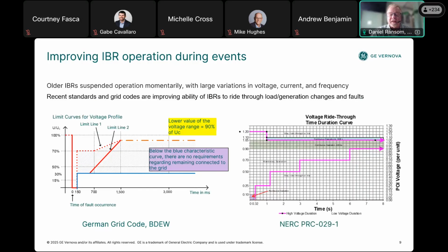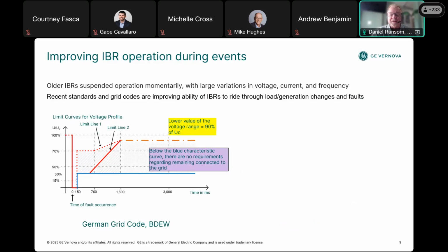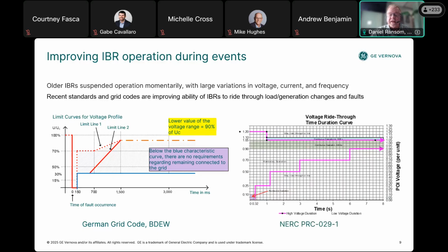It's the figure on the left. The figure shows the limit curves. We'll go back. It's the figure on the left. For type 2 IBRs, PV and BESS, these have to remain connected, as we'll see here in PRC-029-1, during a voltage drop down to 0% Uc for a duration of 150 milliseconds. Oh, that's the one on the right.